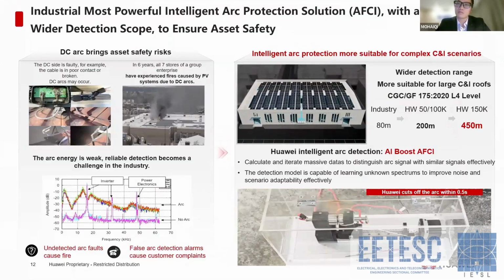One of the standards I want to share is CGC/GF 175:2020. This standard is based on different power levels. For example, whether your system is within 100 kilowatts, between 100 and 200 kilowatts, or more than 200 kilowatts, there will be different detection requirements and also different arc disconnection requirements. If in the future you want to verify whether an AFCI belongs to the premium version, standard version, or basic version, this is a good example for people to check.